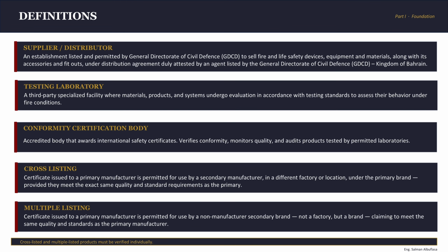A conformity certification body is different from a testing lab. This is the body that awards international safety certificates. It doesn't just test a specimen, it verifies conformity, monitors quality over time, and audits through a surveillance program. For example, UL, FM, LPCB. And here is where it gets confusing, the cross-listing and the multiple listing. This is the part that trips a lot of people up. So, we'll simplify it with an example.